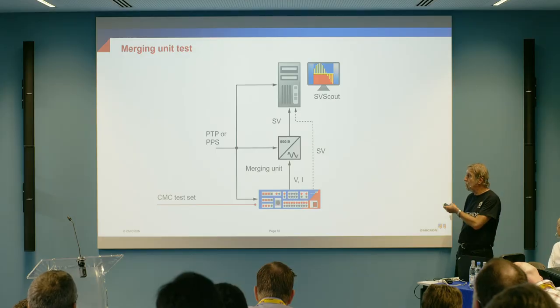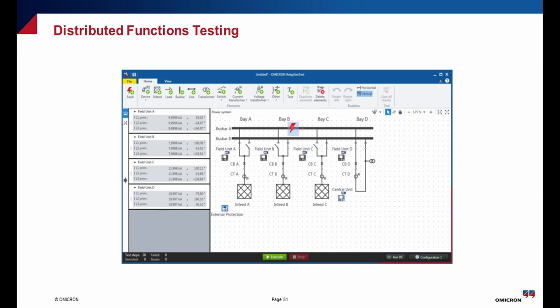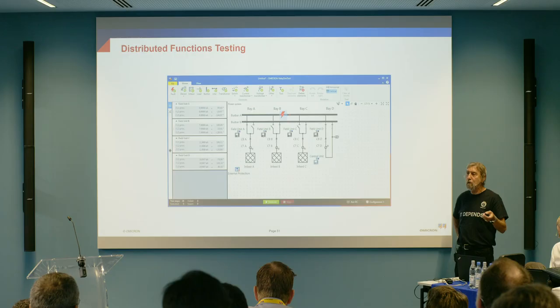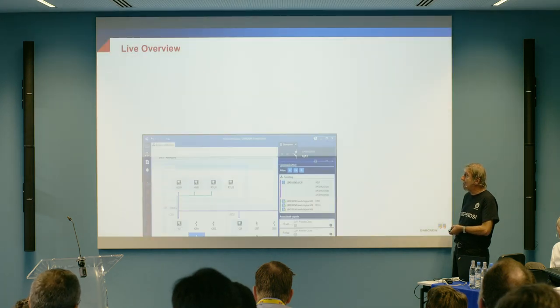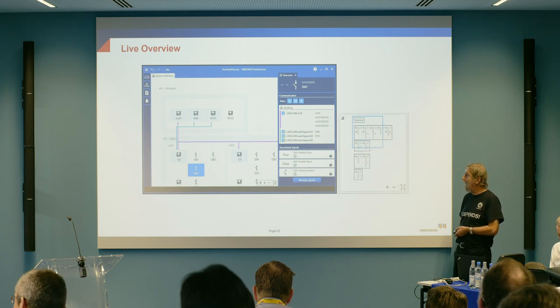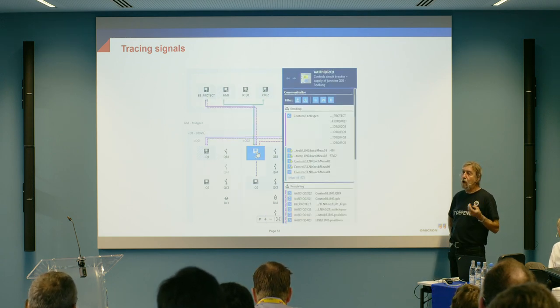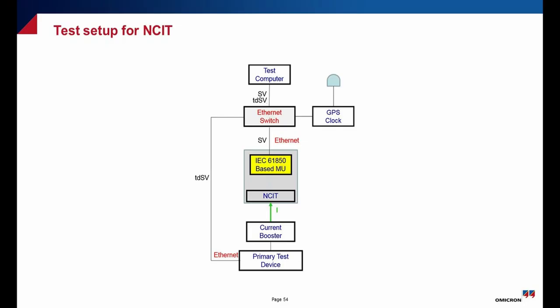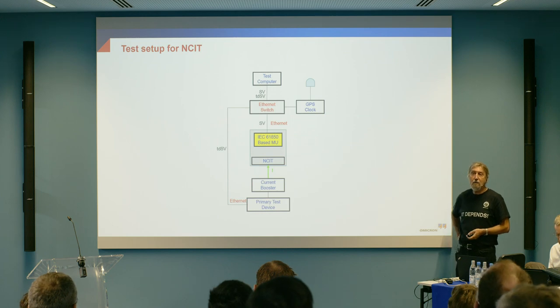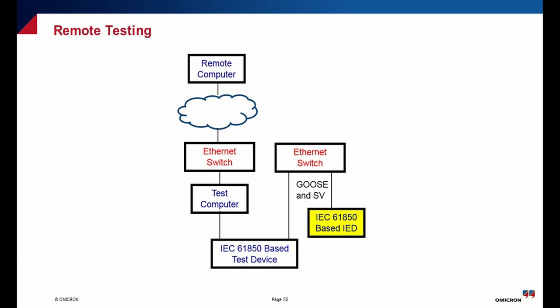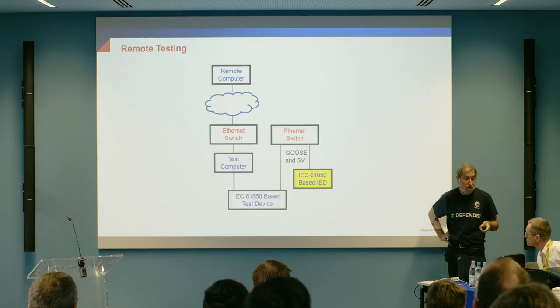It is very important to have tools for testing merging units, tools that allow you to test distributed applications within the substation, between substations, in wide area networks, system integrity protection schemes, etc. Or to have a live overview of what is going on in the substation and to trace different signals in order to identify any potential problems. Having proper tools is a very critical step required for the successful implementation of the standard. In digital substations with non-conventional sensors, secondary injection doesn't work, so we need to do testing with primary injection as part of commissioning. Another capability is remote testing to eliminate trips to the substation under dangerous conditions.